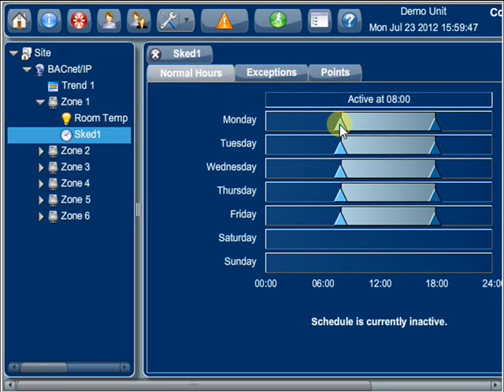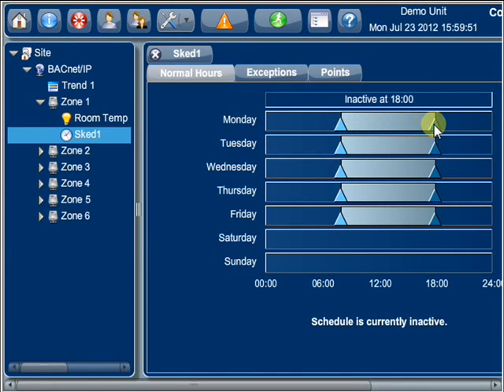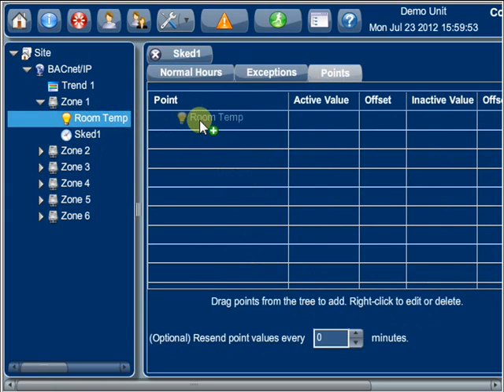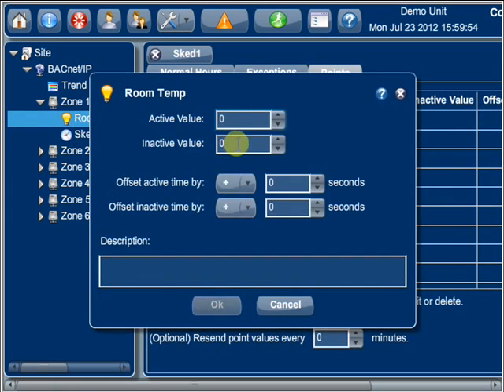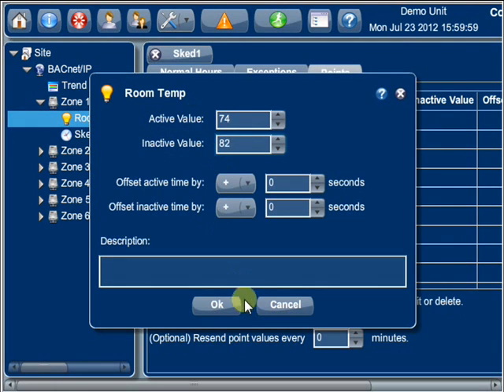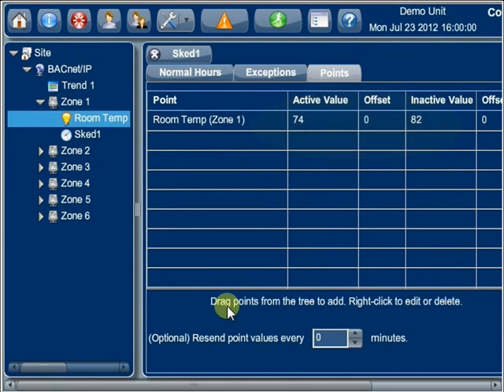...you could set a thermostat to be active between 8 a.m. and 6 p.m. to indicate occupied mode with a set point of 74 degrees Fahrenheit, but inactive at other hours with a set point of 82 degrees to correspond to unoccupied mode. Multiple schedules are supported.